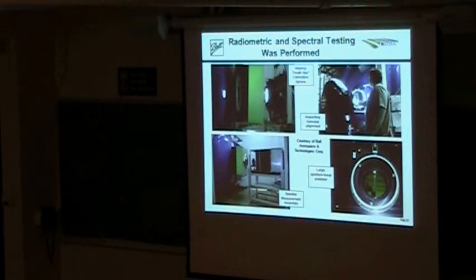So we're going pretty good for time here. This blue here is actually a vacuum chamber. So we have a large vacuum chamber that the whole instrument fits inside. We have a number of these at Ball, and we use those for testing in flight-like conditions, in vacuum, at temperature that you would see if you were actually flying an instrument. And so all of our testing is done within these thermovac chambers. So the challenge is to provide a test platform so that you can actually get the light in and get the data out while the instrument sees flight-like conditions.